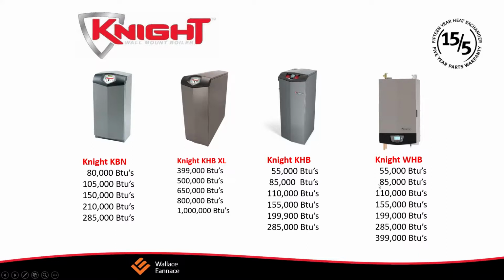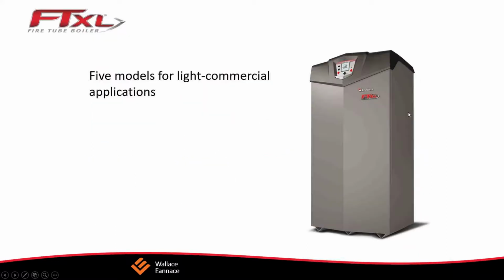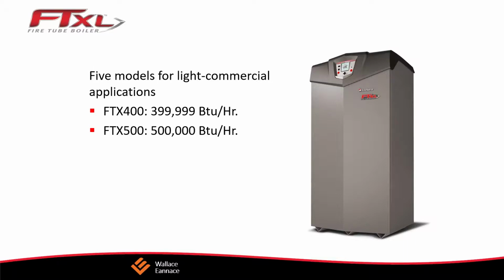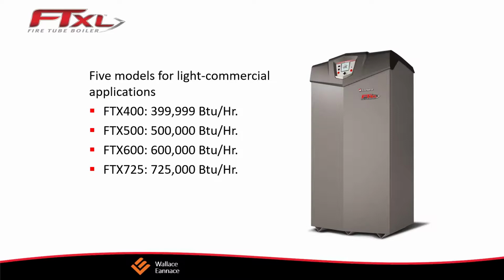Now, let's magnify that in a much bigger building, times 100. Say it's 350,000 or even 3.5 million, for example. At that point, we want to select multiple boilers where we can continue to modulate down to supply small heating loads, because you're going to have a much larger building. Certain areas are going to have solar gain, and there'll be no call for heat over there. Other areas will be colder and chillier, and there will be a call for heat over there. So that deviation will be even greater.